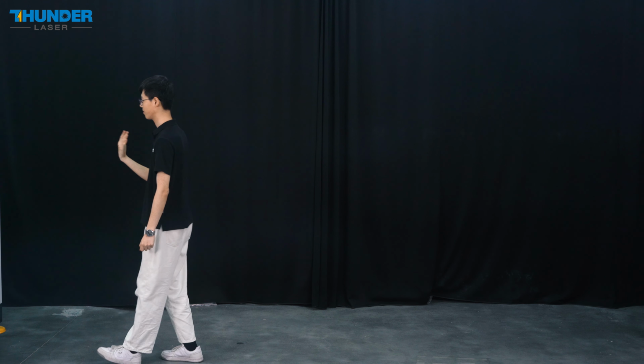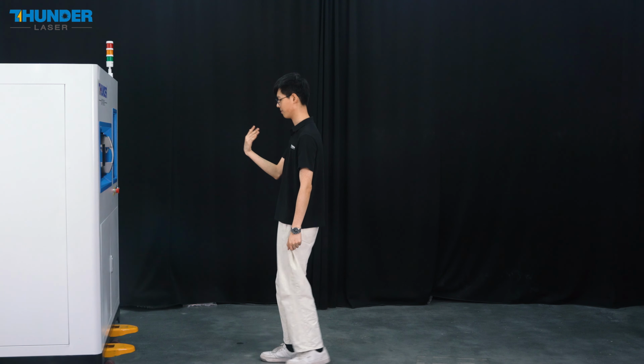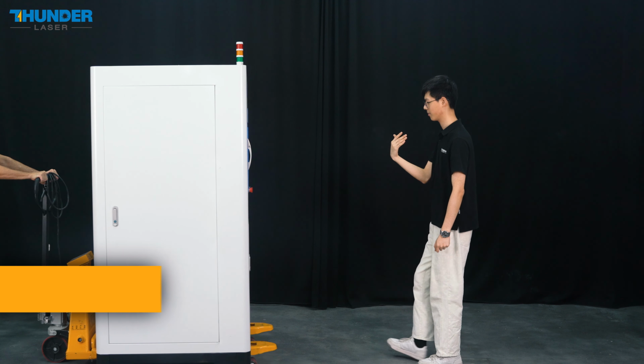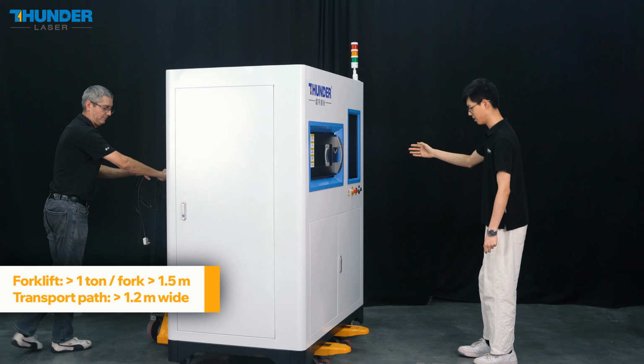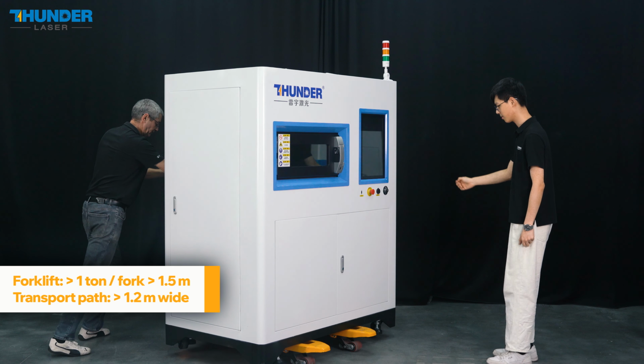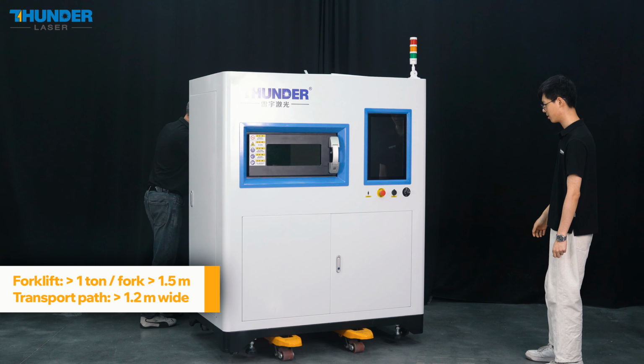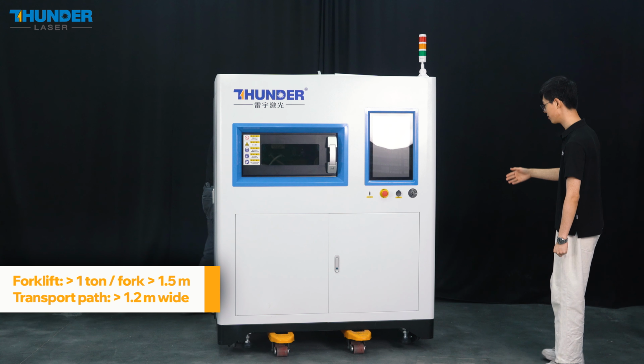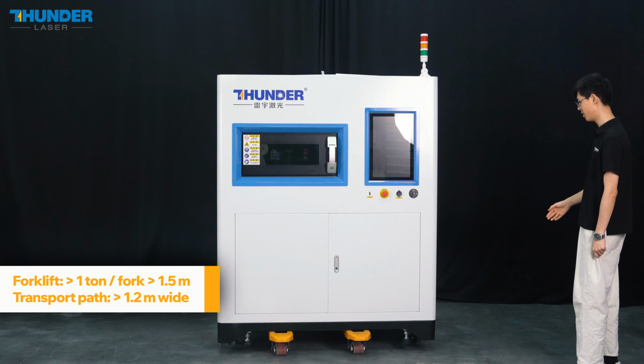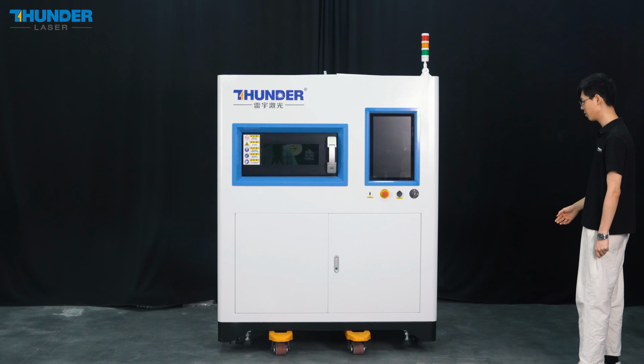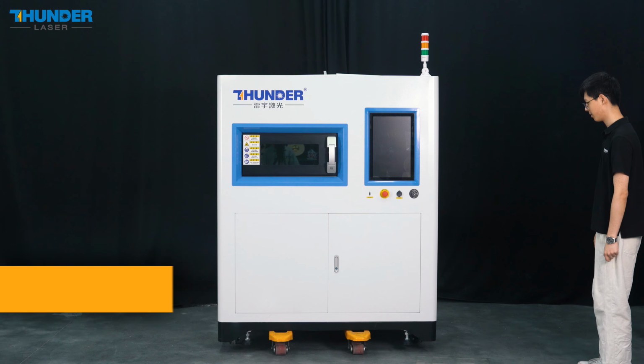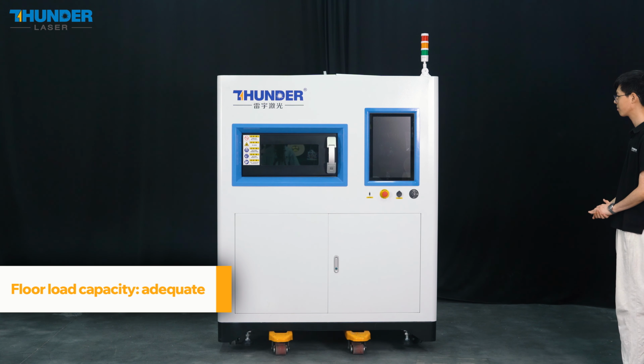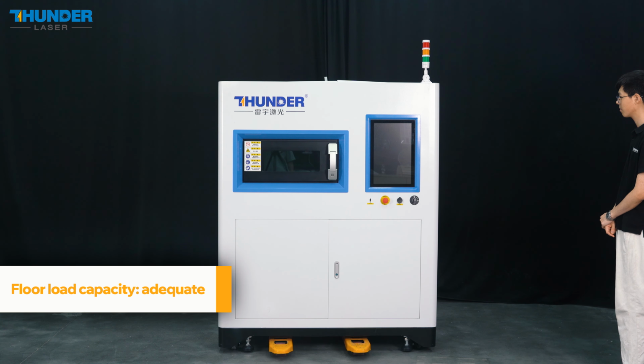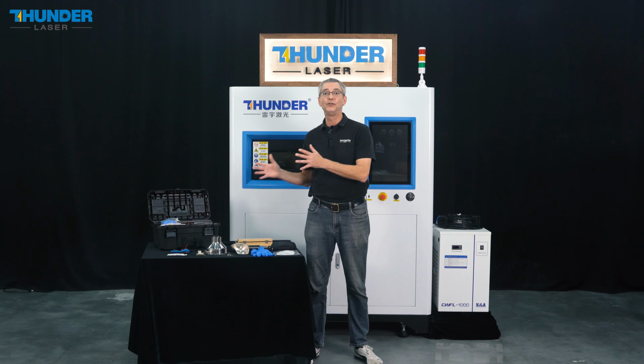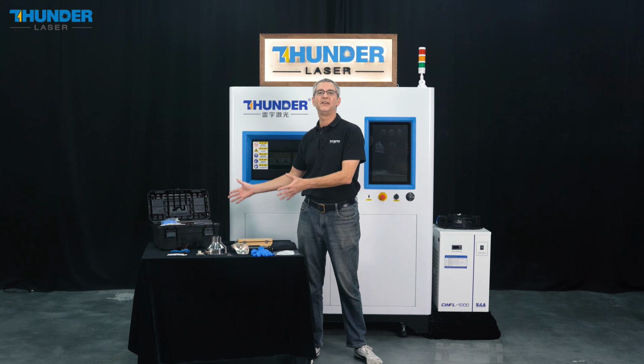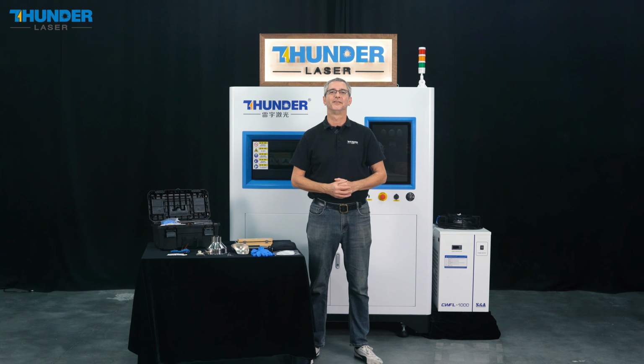The SLM series machine weighs around 530 kg. You will need a forklift with at least 1 ton capacity and 1.5 meter fork length. The transport path must be wider than 1.2 meter. Once the machine reaches its final position, lower it carefully onto a hard, flat and anti-static surface. And keep the keys and toolkit close. Both are needed for what comes next.